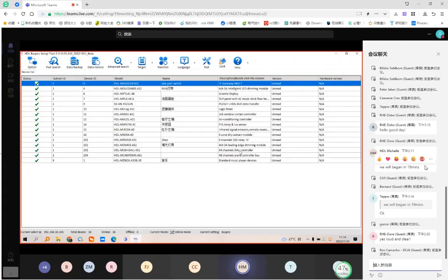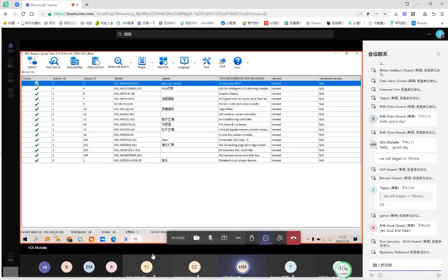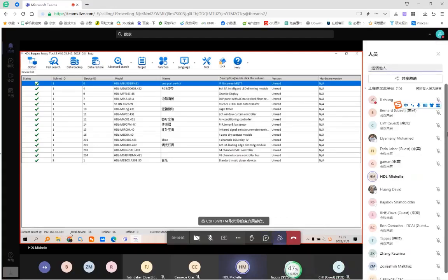Sometimes my customers come across issues where they can't find any device even when they select the same IP. At this time, you can long press the PROG button for 15 seconds, and it will reset to the original IP, which is 192.168.10.250.